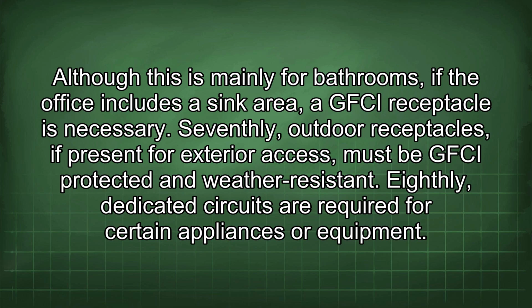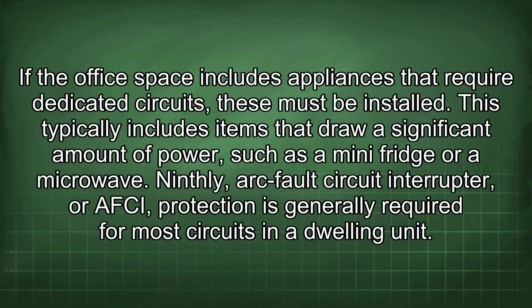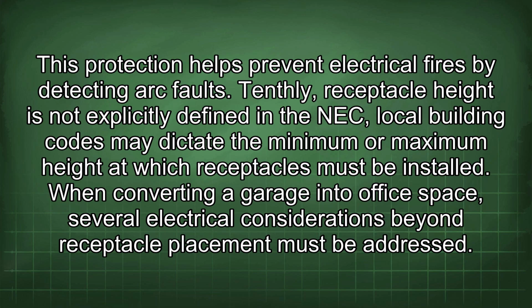Eighthly, dedicated circuits are required for certain appliances or equipment. If the office space includes appliances that require dedicated circuits, these must be installed. This typically includes items that draw a significant amount of power, such as a mini fridge or a microwave. Ninthly, arc fault circuit interrupter, or AFCI, protection is generally required for most circuits in a dwelling unit. This protection helps prevent electrical fires by detecting arc faults. Tenthly, receptacle height is not explicitly defined in the NEC. Local building codes may dictate the minimum or maximum height at which receptacles must be installed.